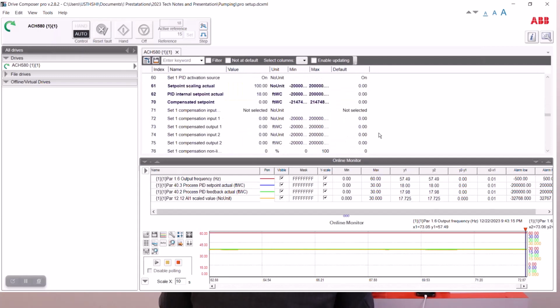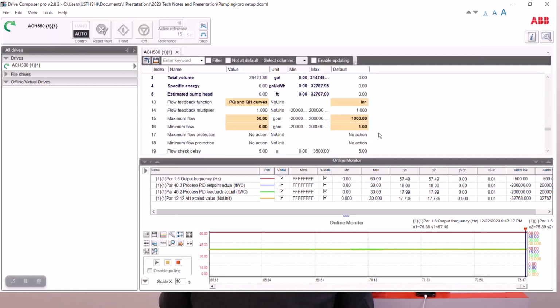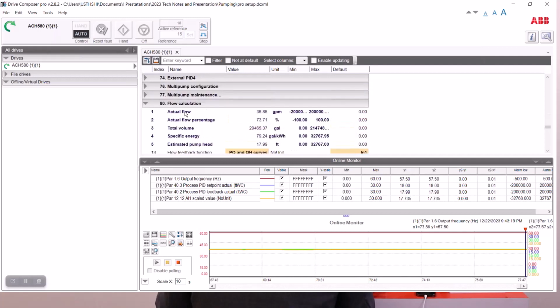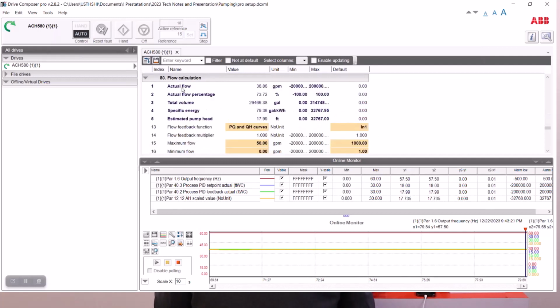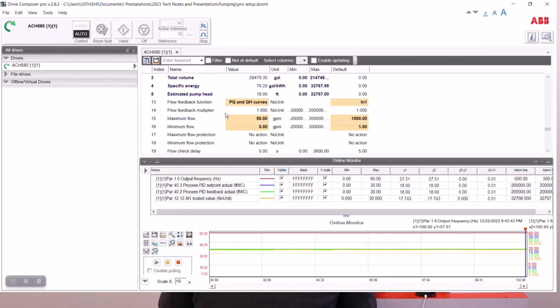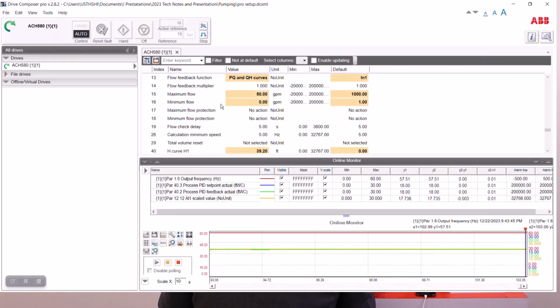If I go down to group 80, looking at group 80 right now, because it's doing an actual flow calculation right here. This is based off of its flow calculation from the data we gave it. And it's claiming it's doing about 36.8 gallons per minute. And I'm sitting here looking at the meter, and the meter says 36.34. So this is an actual flow calculation that it's coming up with. This isn't from the actual meter itself. And it will do total volume and other things. You can adjust this stuff.